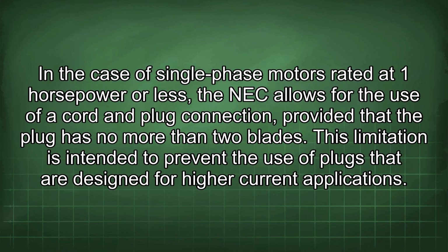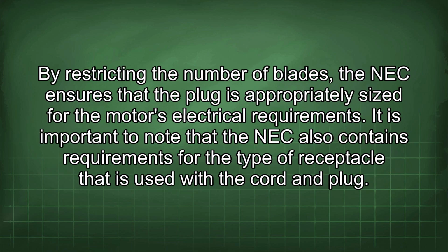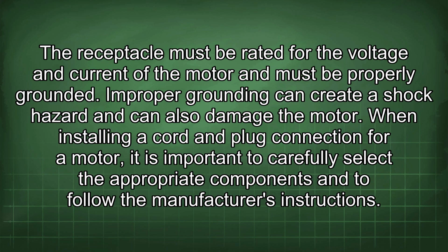In the case of single-phase motors rated at 1 horsepower or less, the NEC allows for the use of a cord and plug connection, provided that the plug has no more than 2 blades. This limitation is intended to prevent the use of plugs that are designed for higher current applications. By restricting the number of blades, the NEC ensures that the plug is appropriately sized for the motor's electrical requirements. It is important to note that the NEC also contains requirements for the type of receptacle that is used with the cord and plug. The receptacle must be rated for the voltage and current of the motor and must be properly grounded. Improper grounding can create a shock hazard and can also damage the motor.